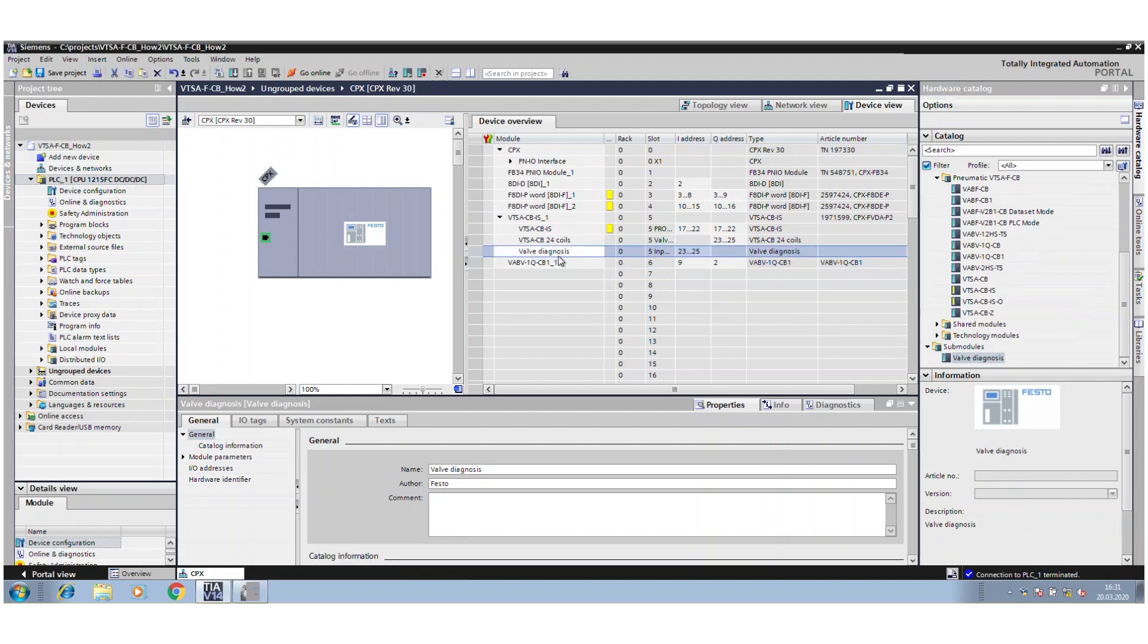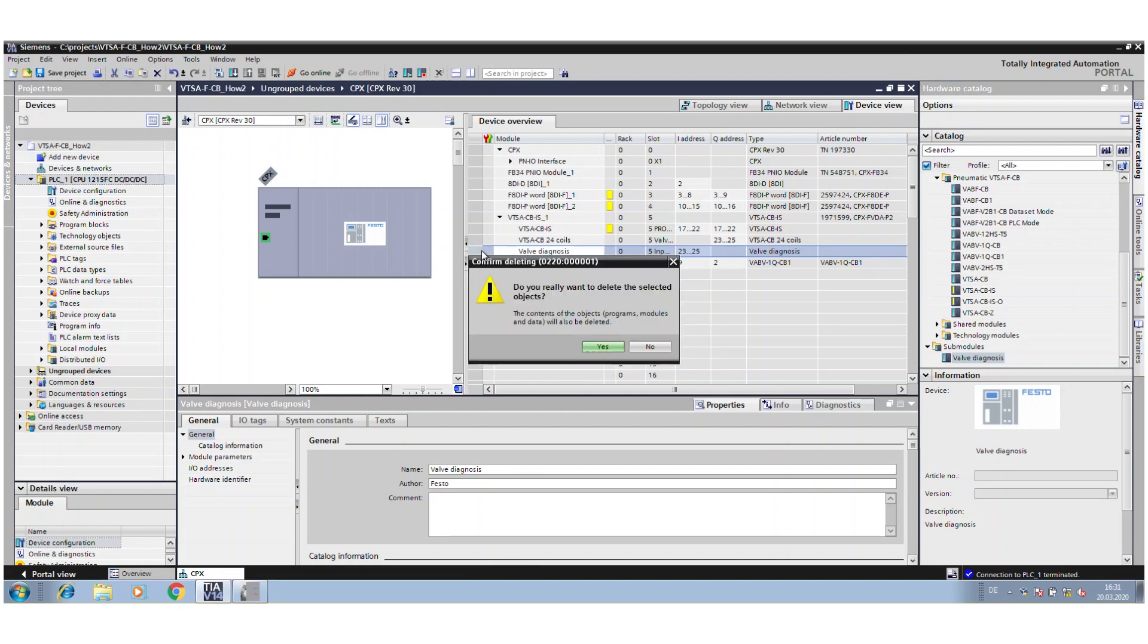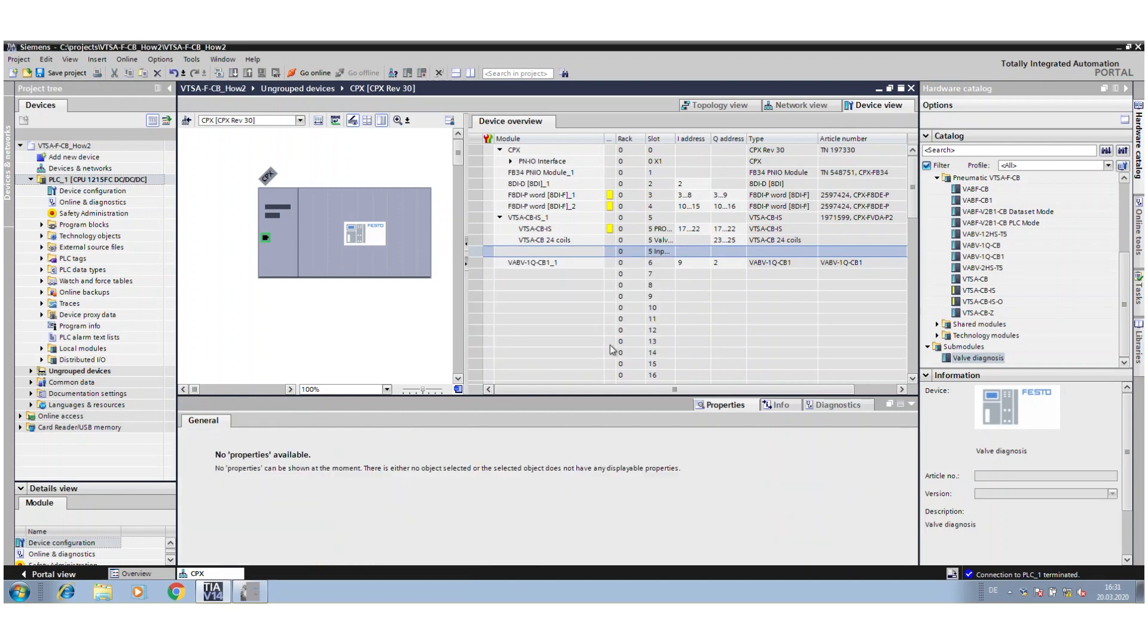When you use this, it opens a new address range for inputs, and there you can get a feedback of failures like short circuit, communication loss, under voltage, and so on. The same you see in the PROFINET messaging system of errors, you also get here as single bits and can use it directly in your program if you want. You can choose it or leave it blank.